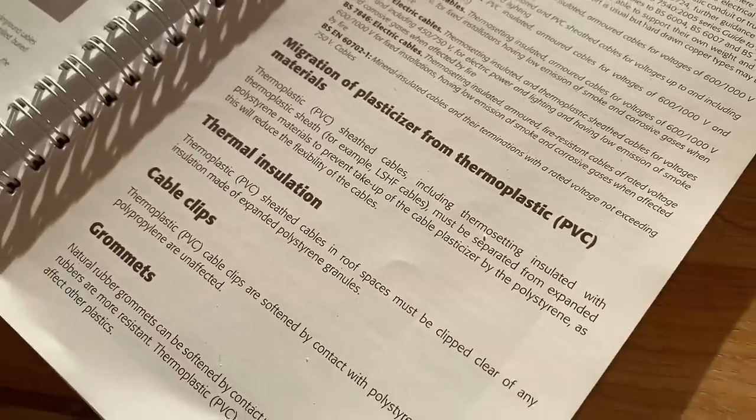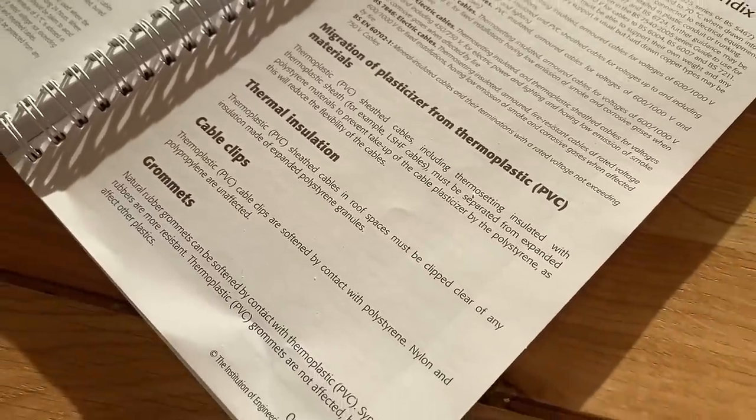The one we're used to is polystyrene beads — cavity wall insulation. Even though you're not necessarily meant to put cables in cavity walls, there's that same reaction in those places as well. So that's caused an issue. And imagine if you hadn't spotted it — if you'd picked up the wiring system to do the second fix thinking all the grunt work had been done.